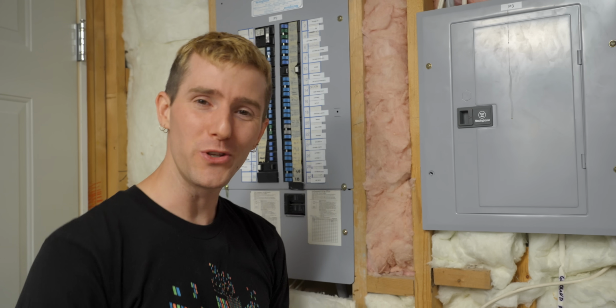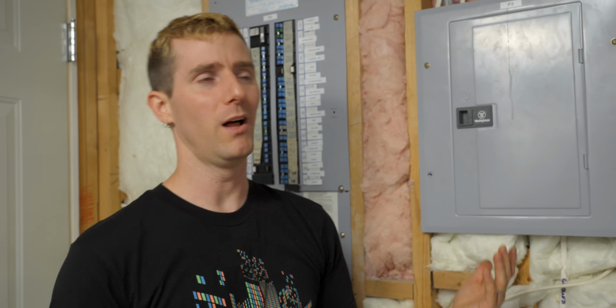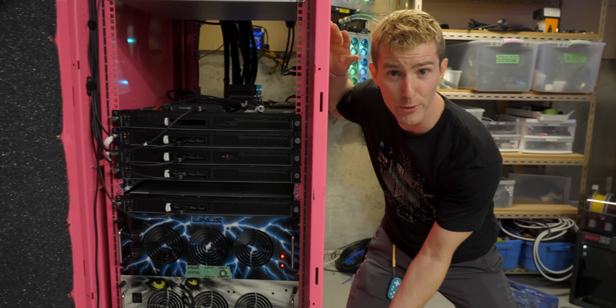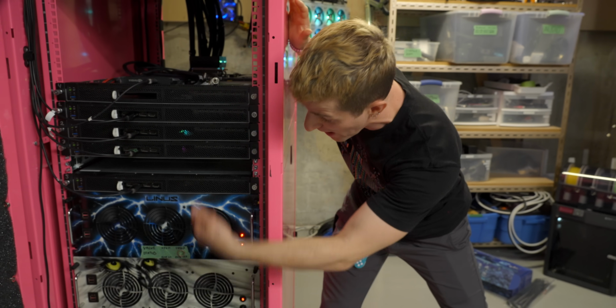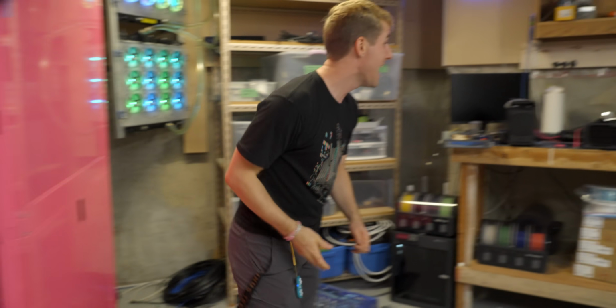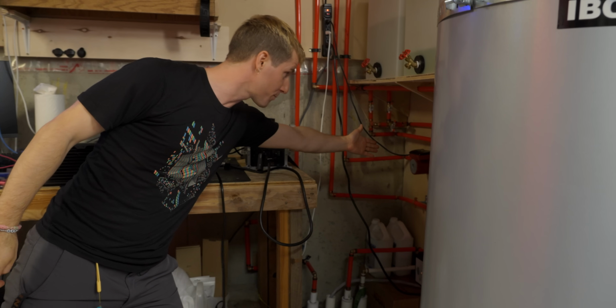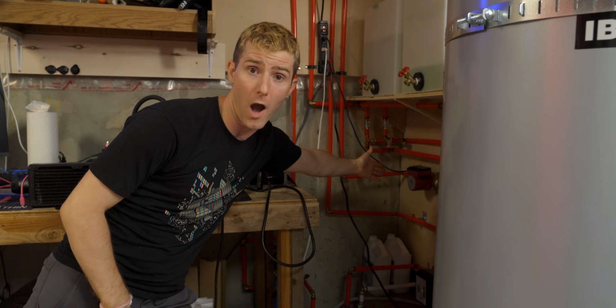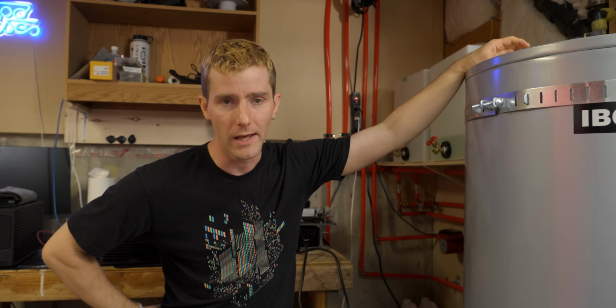Should be fine. The story changes when you apply a voltage, and well, we obviously weren't intentionally doing that. When you have a large power draw in one spot, like a couple thousand watts of computers in a rack, and a low power draw in another spot, like a couple hundred watts from a pump, you're gonna end up with a difference in voltage between them, which accelerates corrosion dramatically and can make compatible metals far less compatible.